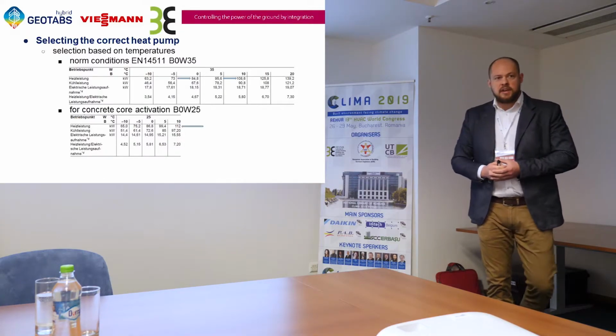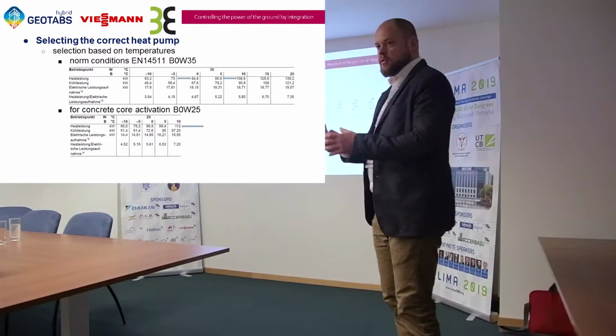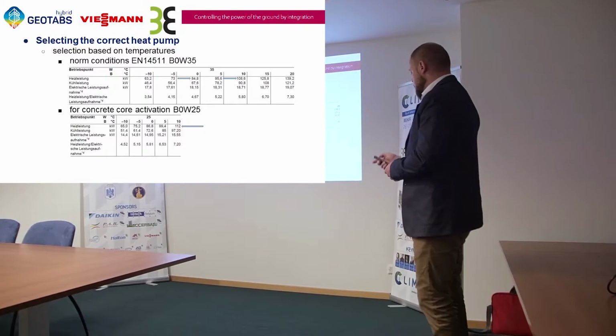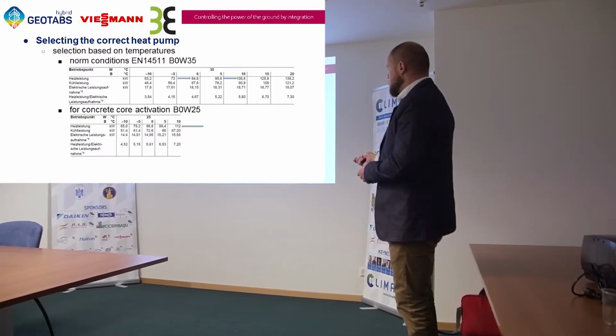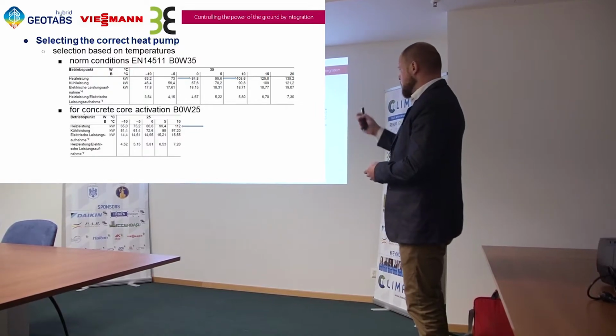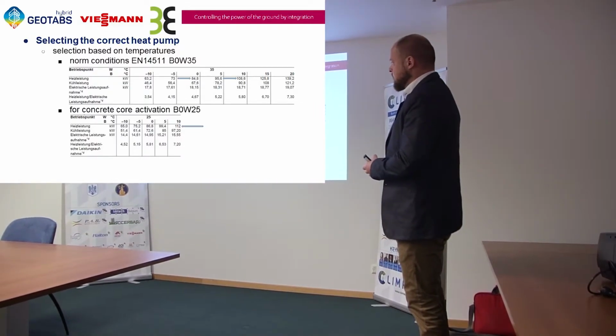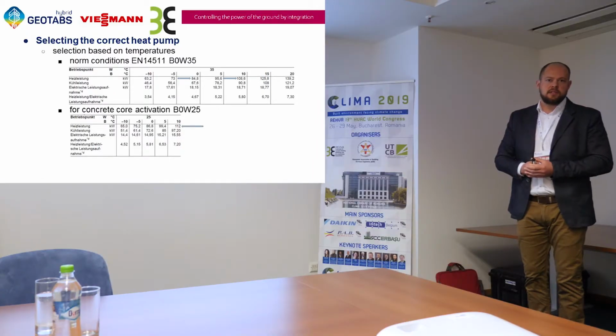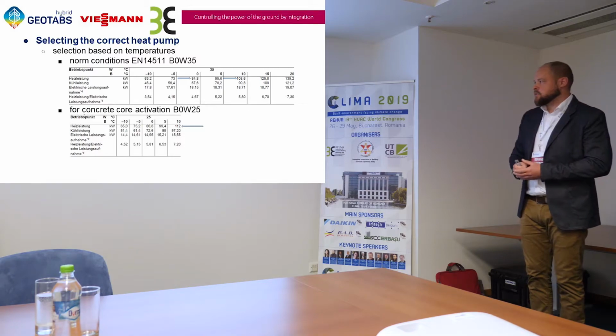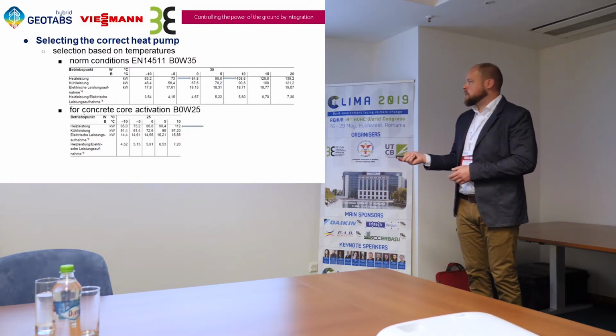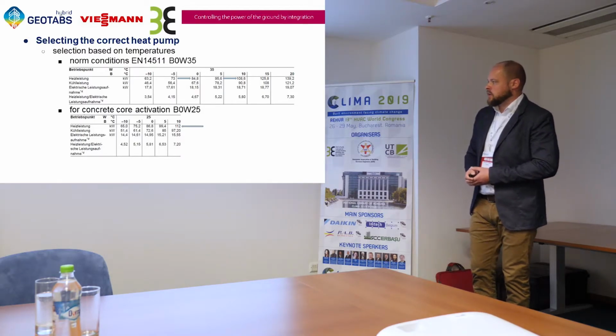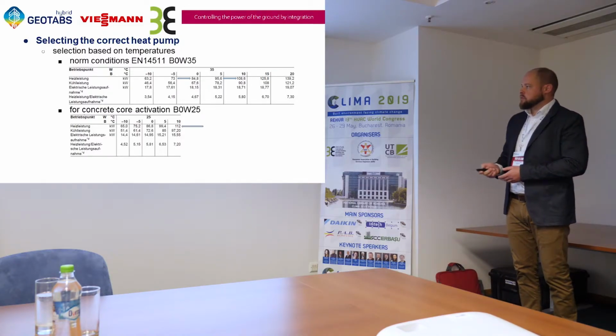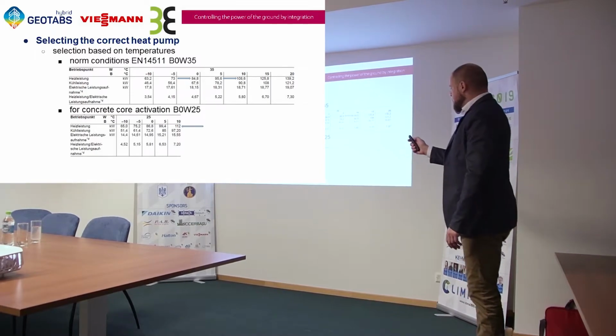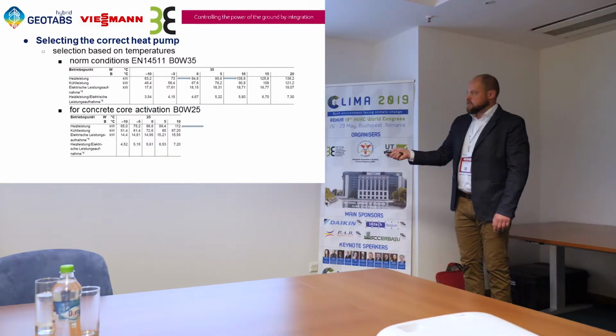Even now, for concrete core activation, Viessmann added a new table, so we test the machines on different working conditions, and we add the table of the source at 0 degrees and the secondary side at 25 degrees. Because for concrete core activation, the temperatures on the secondary side are mostly not higher than 25 degrees. We're going to see that later on in the next presentation. So you can see the same heat pump here at 0.25 gives a little bit more power, but the COP here is a lot higher. So we have 5.8 in comparison to 4.6 there. Even here you see when we have an input of 10 degrees and we have 25 degrees departure, on the secondary side we have a power of 112 kilowatts for the same heat pump.